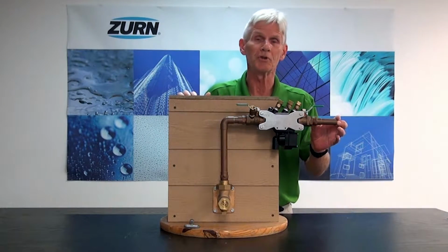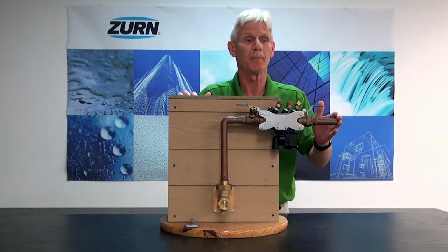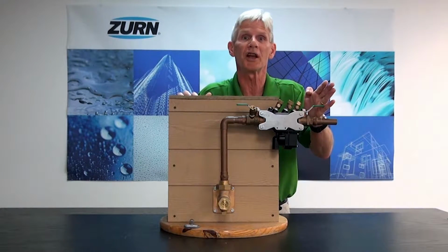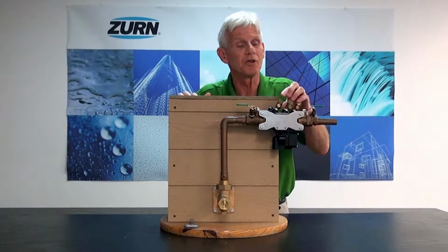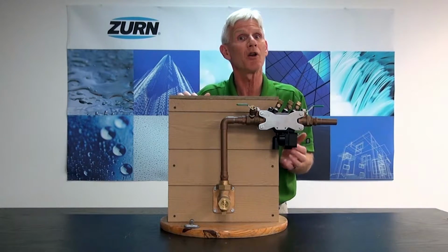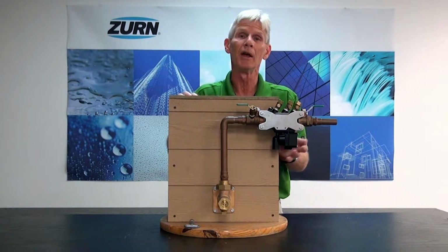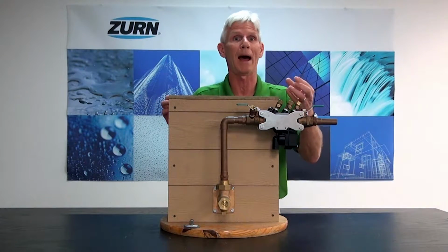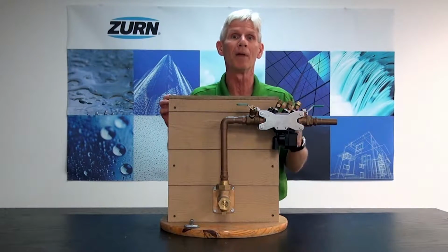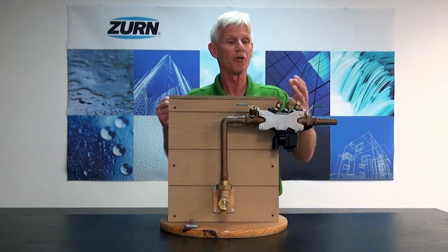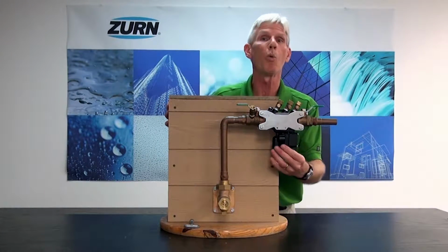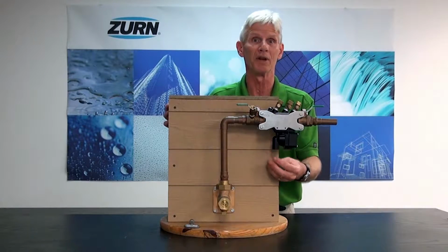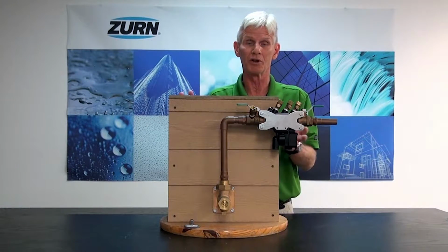Also on the downstream side, if I have an increase of downstream pressure, that pushes against my second check valve, and that causes the pressure in the zone to rise, and that can also give me relief valve discharge. But in both of those cases, the relief valve discharge is generally finite. It's going to dribble a little bit and then it will stop. What I'd like to do is diagnose those conditions whereby we see water continually coming out of the relief valve, and it's pretty straightforward to do so.